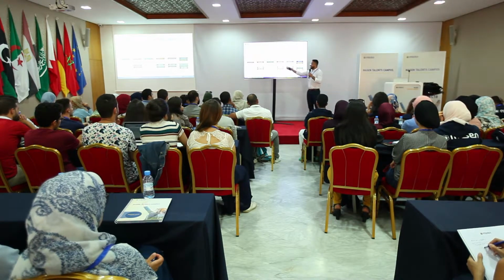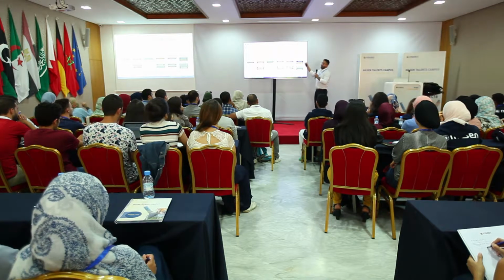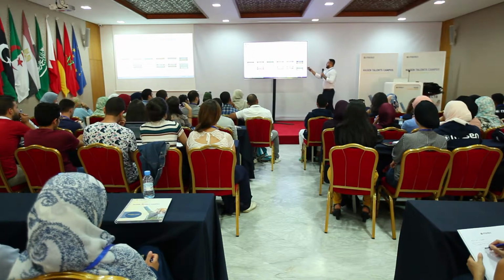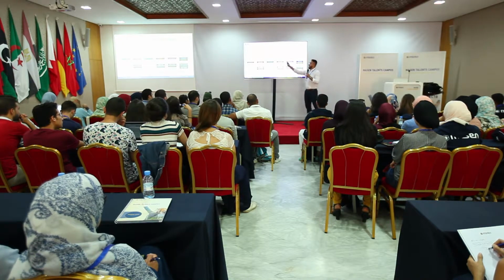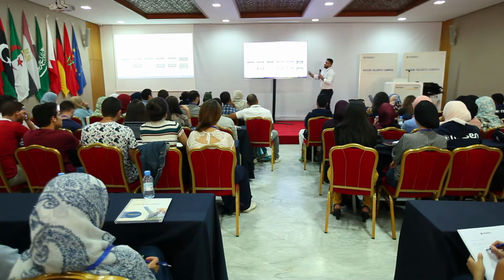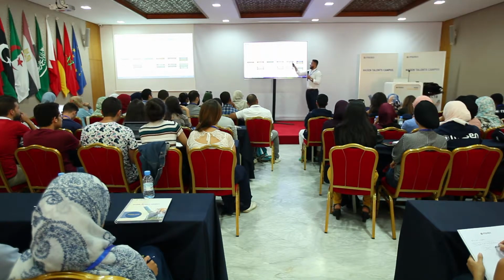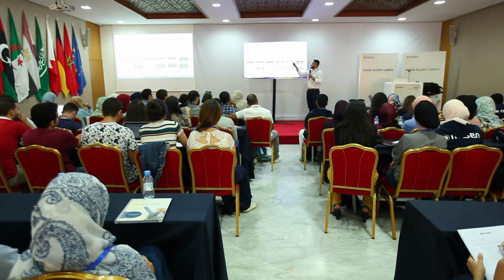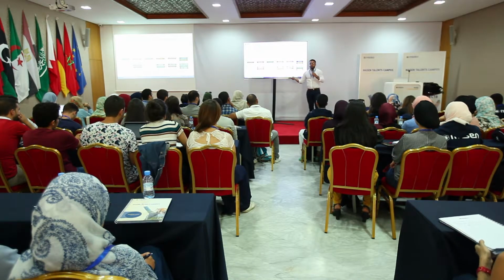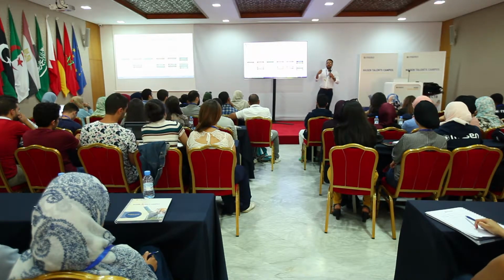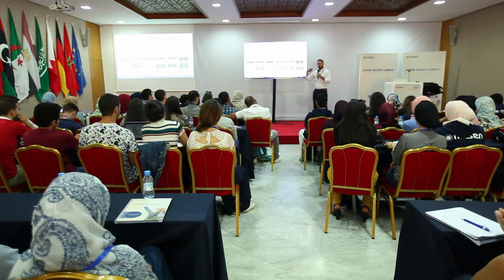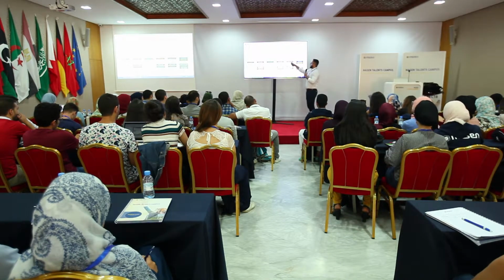Actually, I don't really know the answer because it's not my field. But it's around 30%. Just think about it: the PV plant operates only when there is daytime because there's no storage. And even in daytime, it maximizes output only when there's the most irradiation, which is solar noon. The rest of the time it's producing less or not producing at all. So the capacity factor for a PV plant maximizes at 34% with a tracking mechanism.